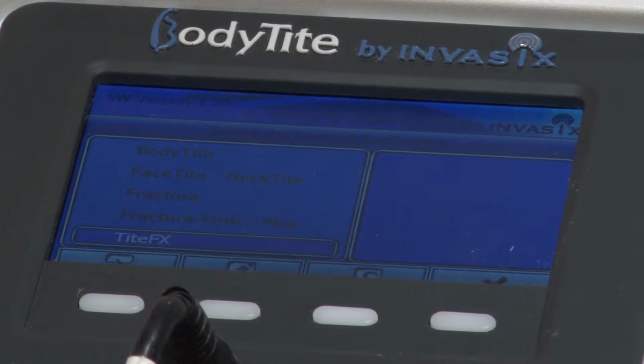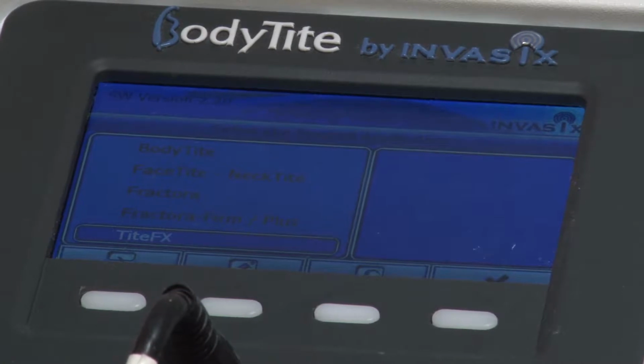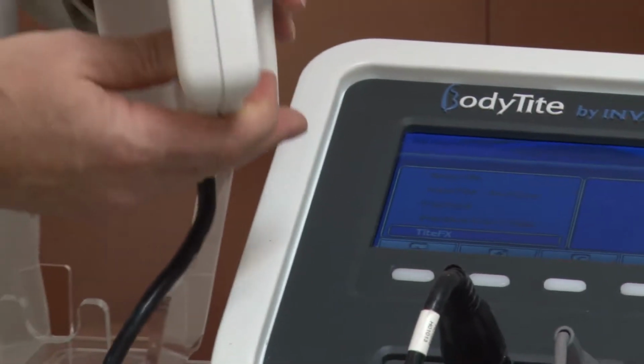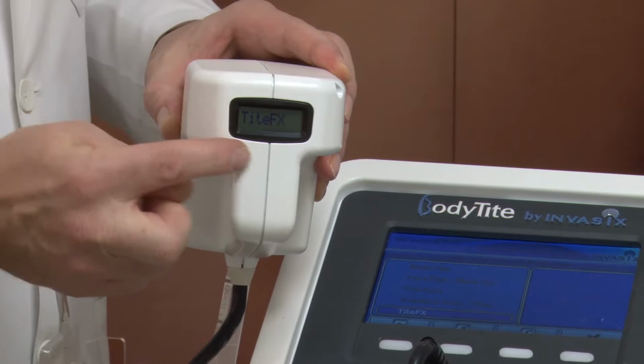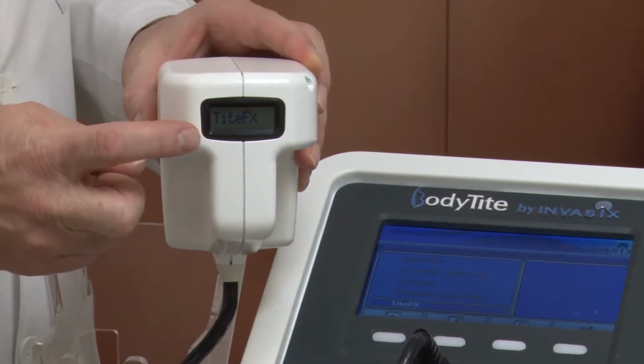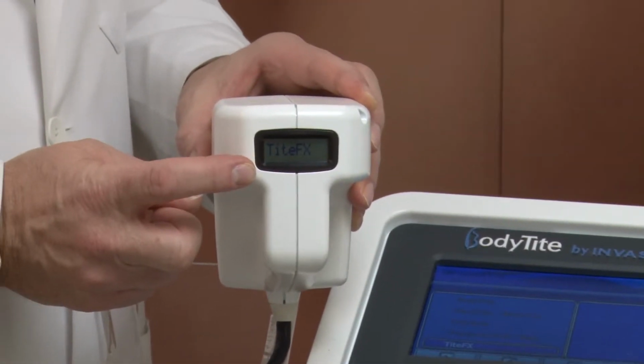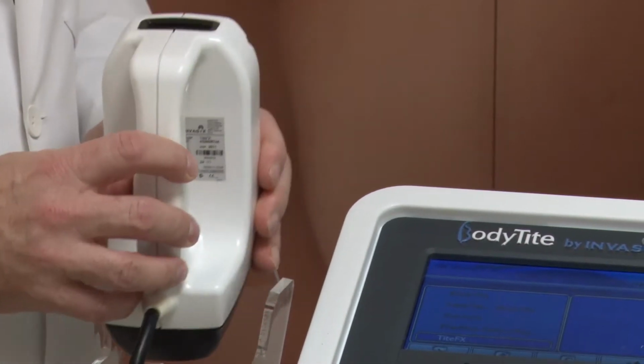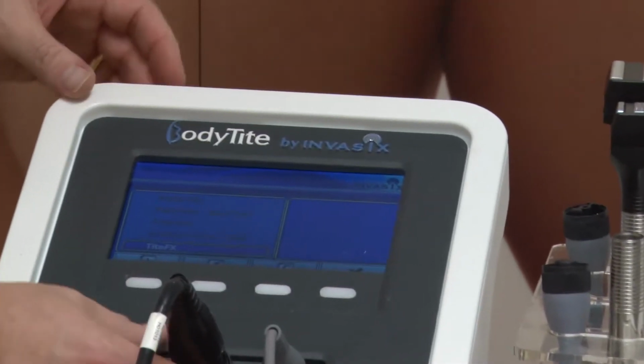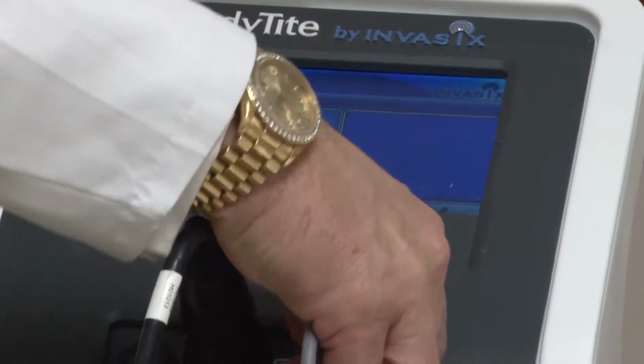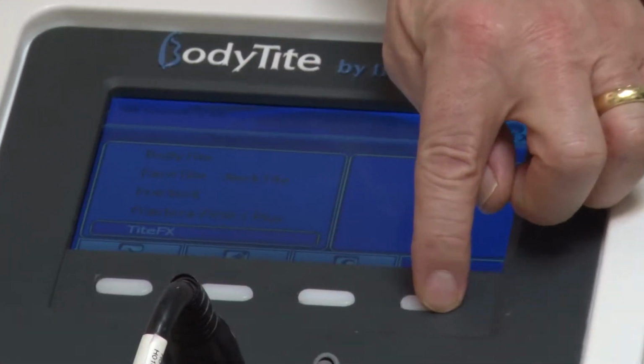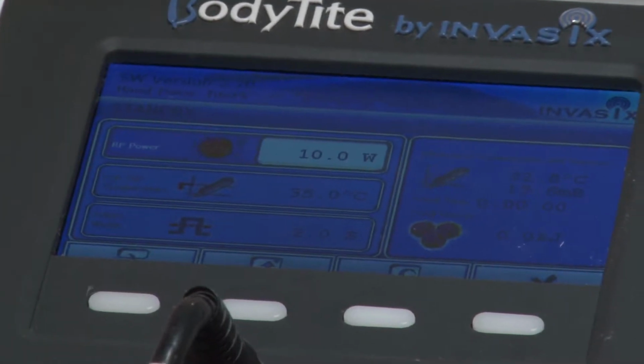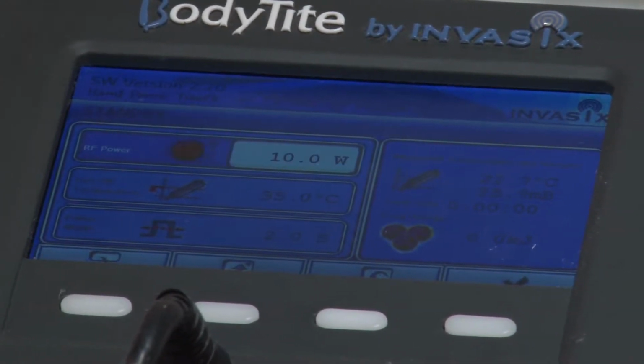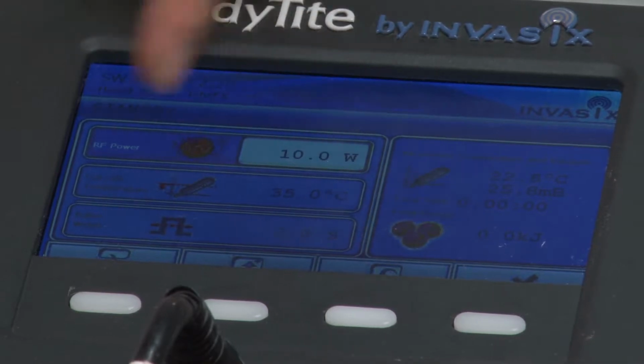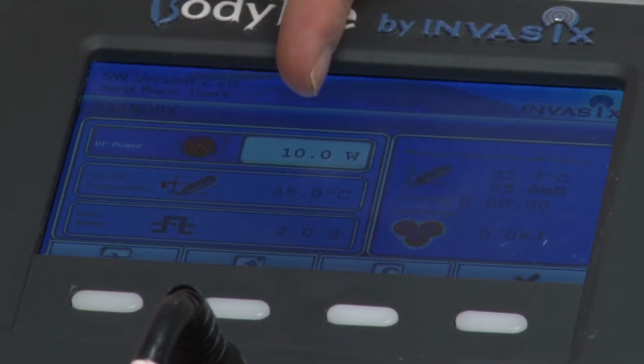When the TiteFx is plugged in, you will see on the top of the handpiece that it's activated. It says TiteFx. This little LCD display screen will also tell you the tissue temperature at any given time. Let's put that down now and go back to the screen. When you want to use the TiteFx, and that's the one you have activated, you simply hit the check mark and up will come the TiteFx screen. Now, you'll see during the webinar, we control the amount of energy, the number of watts we're going to use. I typically treat at 50 watts, so we'll dial that up to 50.